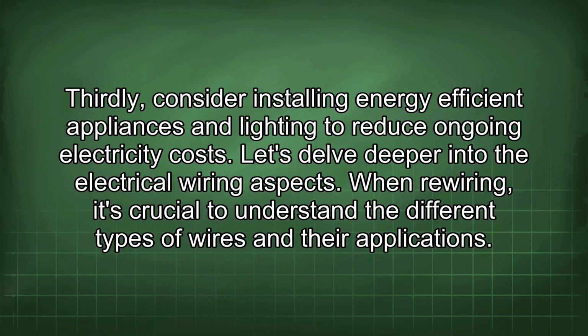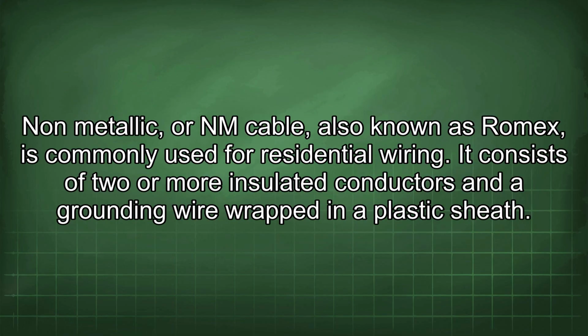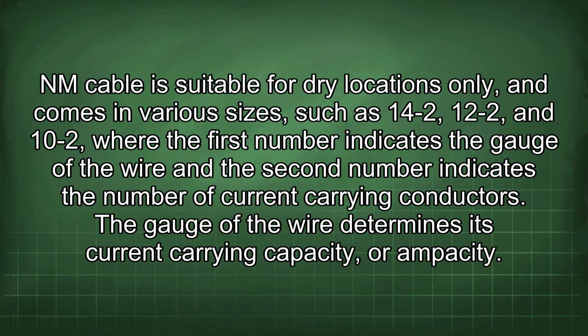When rewiring, it's crucial to understand the different types of wires and their applications. Non-metallic, or NM cable, also known as Romex, is commonly used for residential wiring. It consists of 2 or more insulated conductors and a grounding wire wrapped in a plastic sheath. NM cable is suitable for dry locations only, and comes in various sizes, such as 14-2, 12-2, and 10-2, where the first number indicates the gauge of the wire and the second number indicates the number of current carrying conductors.